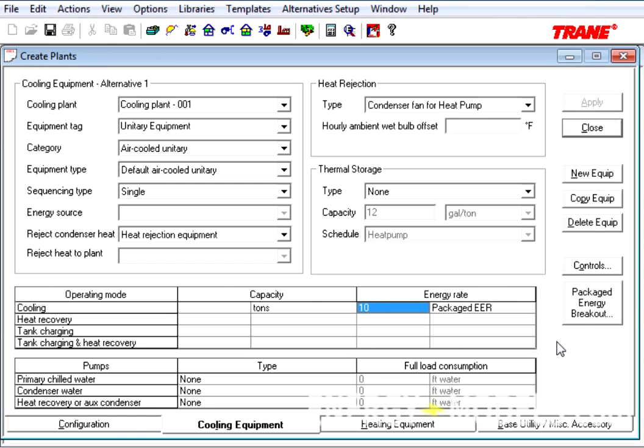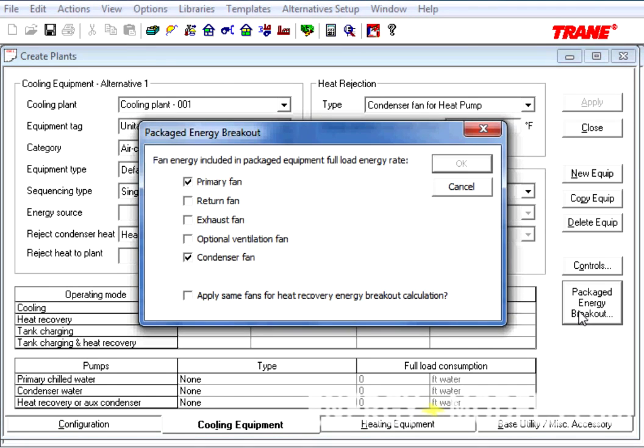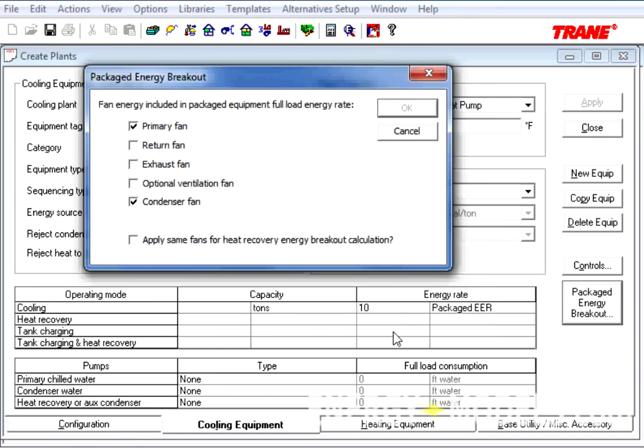Now, the Packaged Energy Breakout button is available. Upon clicking it, it will ask us which fan energy should be included in the Packaged Equipment Full Load Rate. For instance, this value of 10 EER includes what fans? In general, it's the primary fan and the condenser fan.